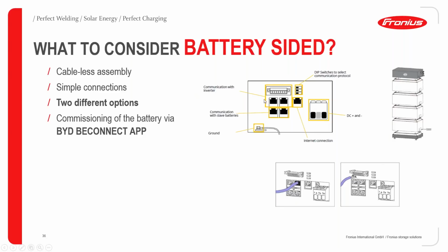Then there are the communication ports with the inverter, where you have two different options. On one hand, you can cut a Cat5 cable on one end, plug it in, and connect the cable directly to the Modbus plug of the Fronius inverter. Or you can use a 4-pole cable with this communication terminal at the top, with pins where you can easily connect it.